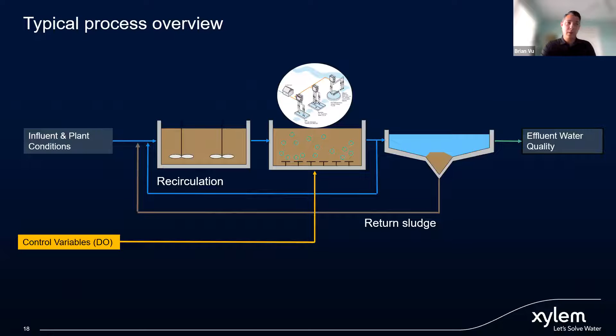So you get into some more advanced controls, a feedback loop. You're using that same type of control system. You got influent coming in. You got some DO control here, sending a set point back to SCADA. And then you can take your ammonia probes. Let's say you place some ammonia probes in your final effluent. You can get an ammonia signal. That's really what you're treating for, right? Not DO, but ammonia. Sending that ammonia signal back into SCADA, and then that can send a signal back into your blowers to ramp up and down based on ammonia loading on the back end. So that's a typical feedback control.